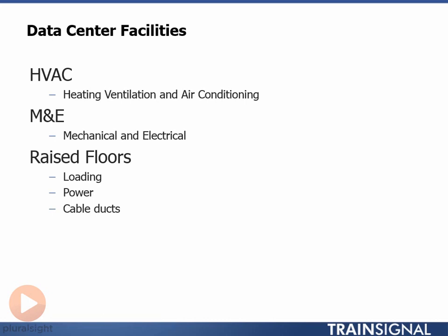But raised floors are made by resting square floor tiles on top of metal stilts, meaning that you need to be careful how much weight or load that you place on them. Make sure that the equipment you stand on them isn't too heavy for them, as raised floors absolutely can collapse if you put too much weight on them.